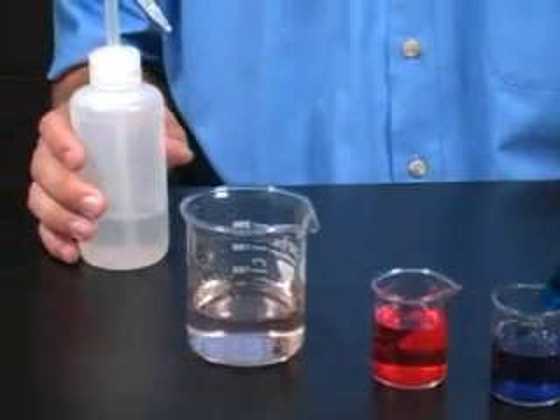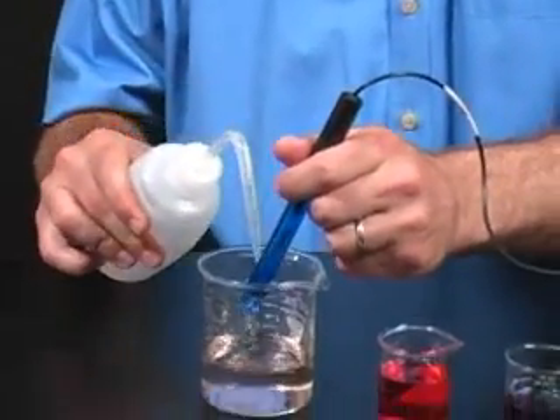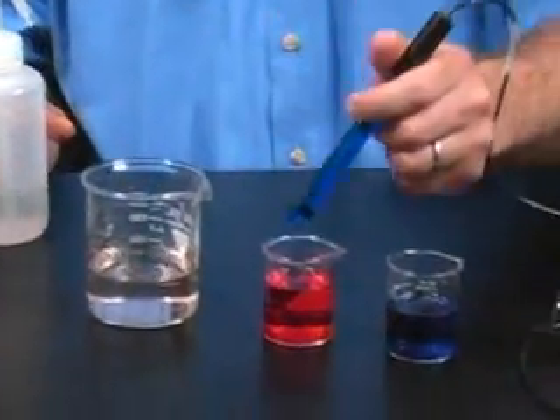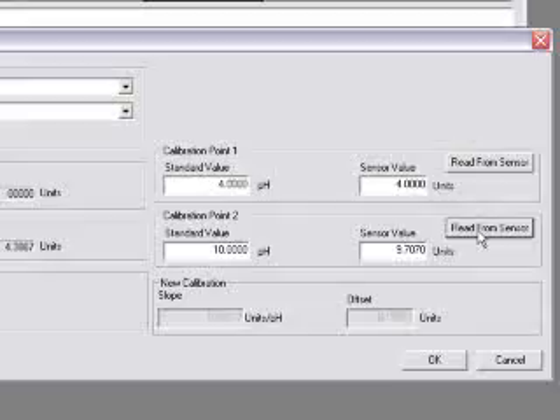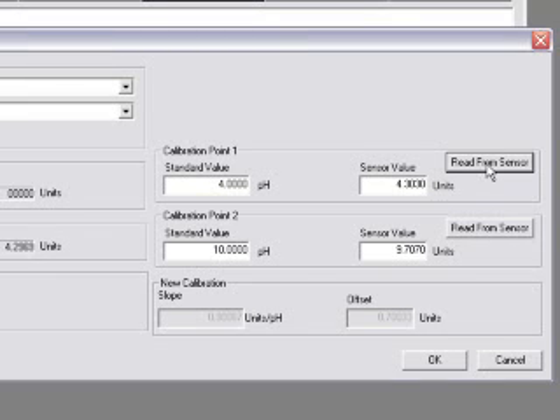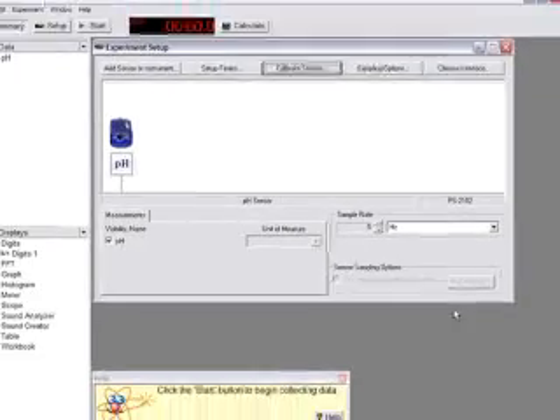We'll then remove the probe from that solution, rinse, and place it in our second pH buffer solution. In the Calibrate Sensors window, click the Read from Sensor button in the box corresponding to that pH value. Again, you'll notice that the sensor value has changed. After having done this, click OK, and the calibration information has been recorded, and we are now ready to take measurements.